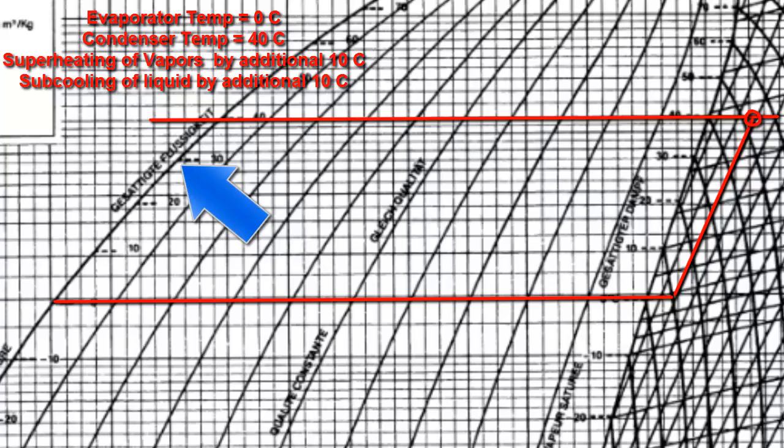On the left-hand side, note that the condenser is operating at 40°C, but the refrigerant leaving the condenser is sub-cooled by an additional 10°C. So 40 minus 10 will be 30°C — that will be the discharge temperature of the refrigerant from the condenser. We identify 30°C on the saturated liquid curve and draw a vertical constant temperature line to where it meets the condenser line, extending it all the way to where it meets the evaporator line.